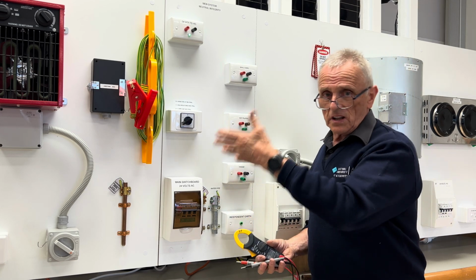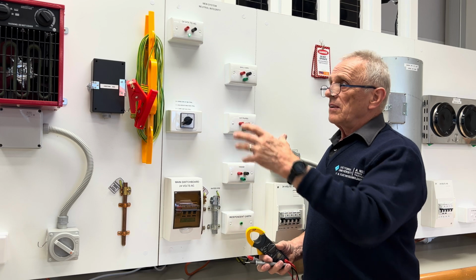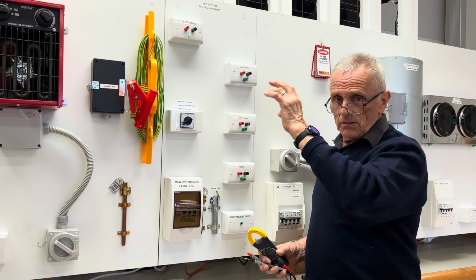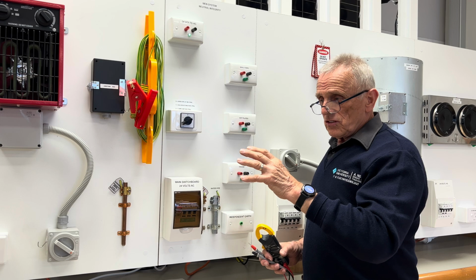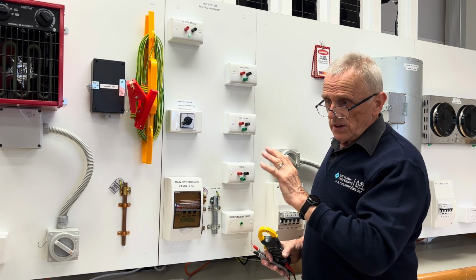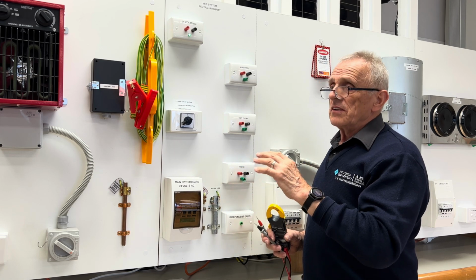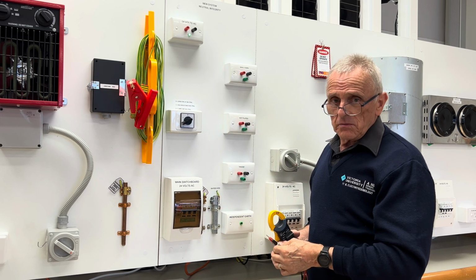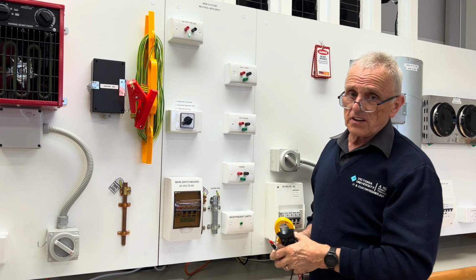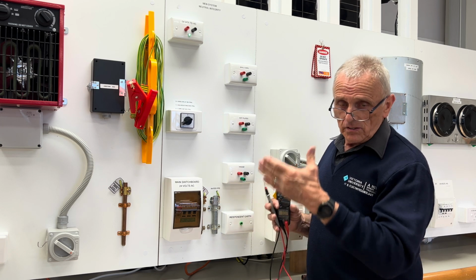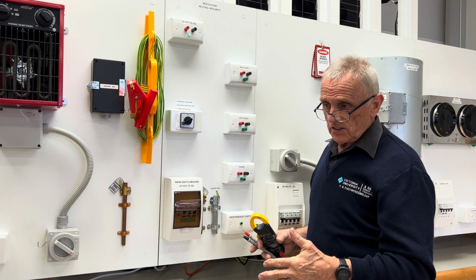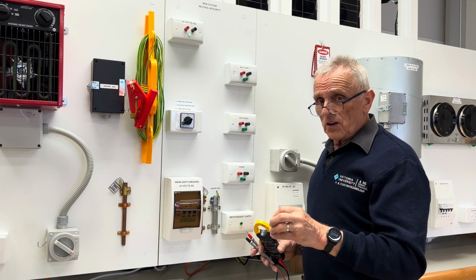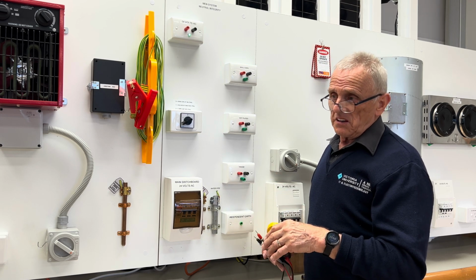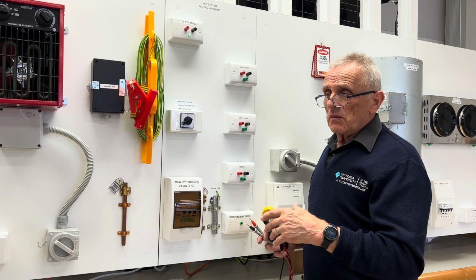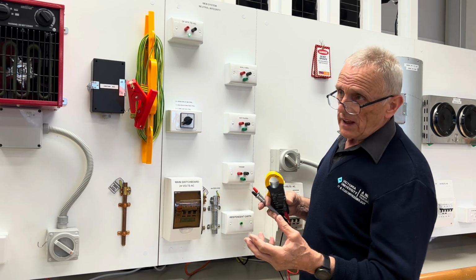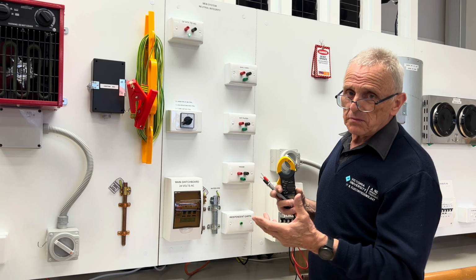This represents a good installation, meaning that the main neutral coming in from the street or from the pit is large. There is a very low resistance, very low impedance. Therefore, return current is returning back to the source, to the start point of the transformer, as it should. And we're not having any voltages in the earthing system. There may be 1 or 2 volts, which is well below the maximum voltage we require. We always have some voltage because there is never a perfect main neutral.